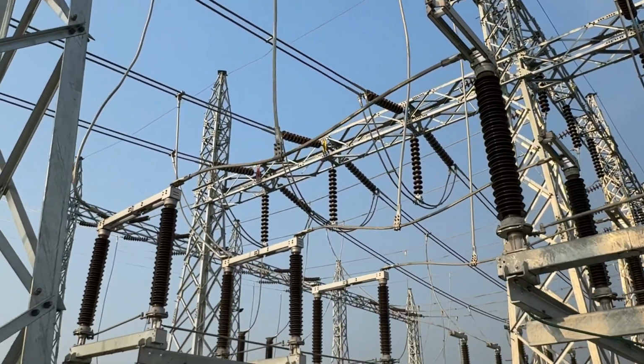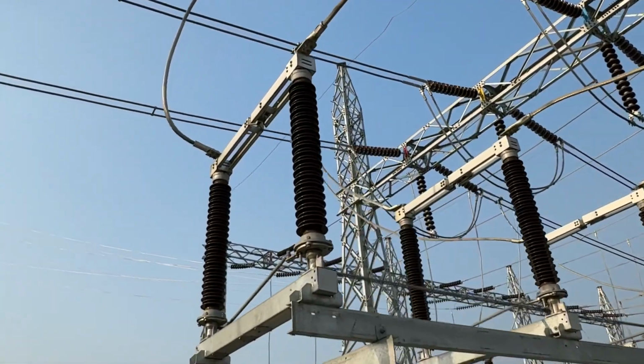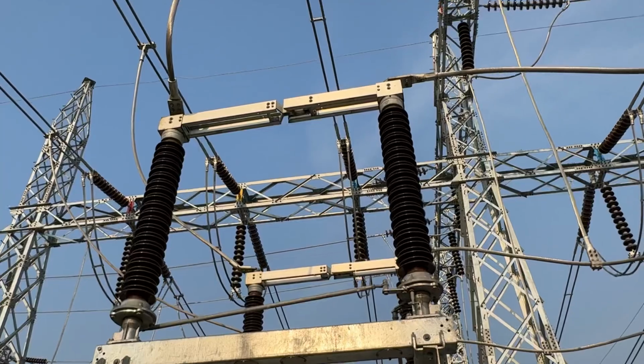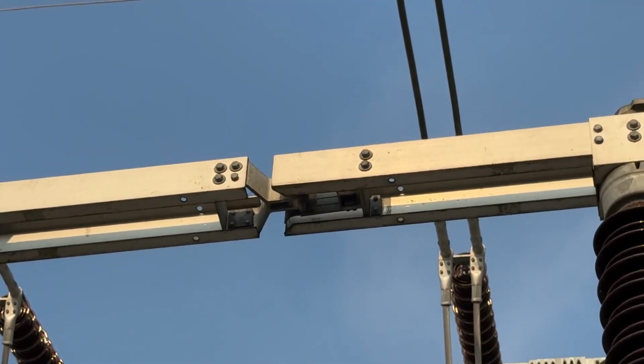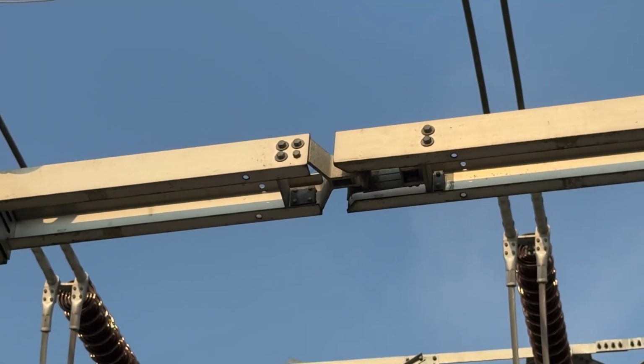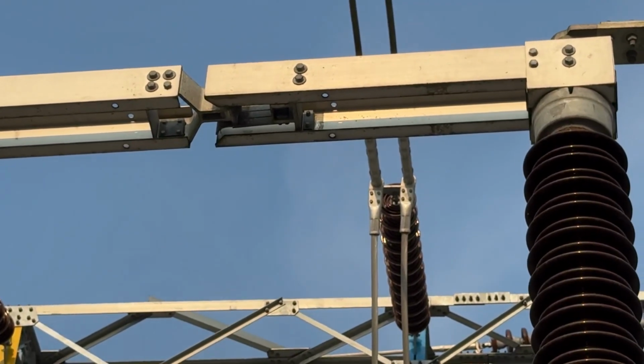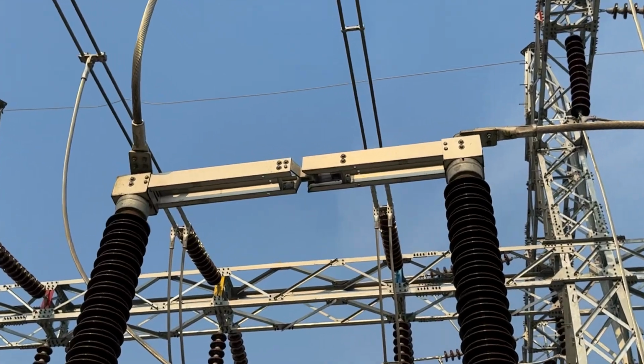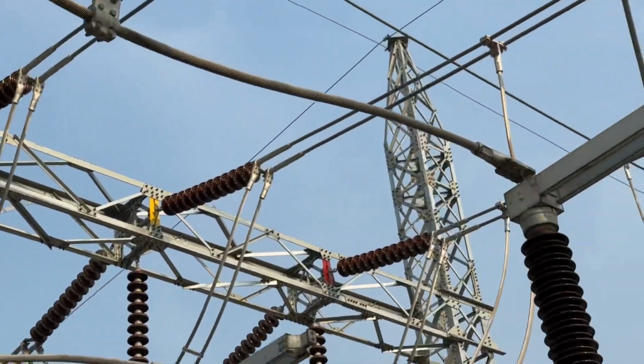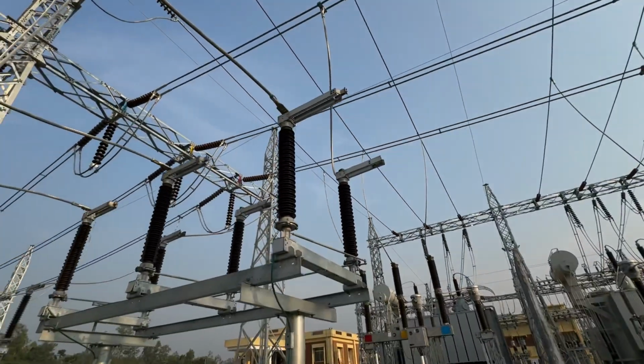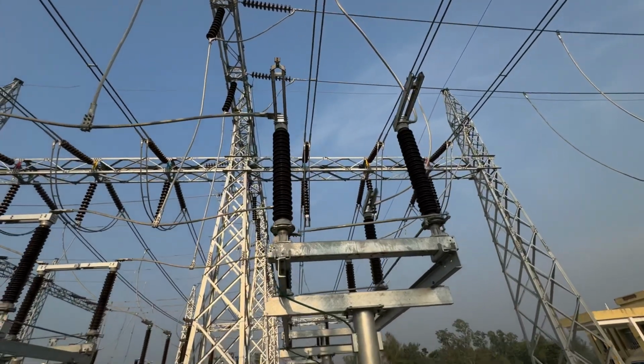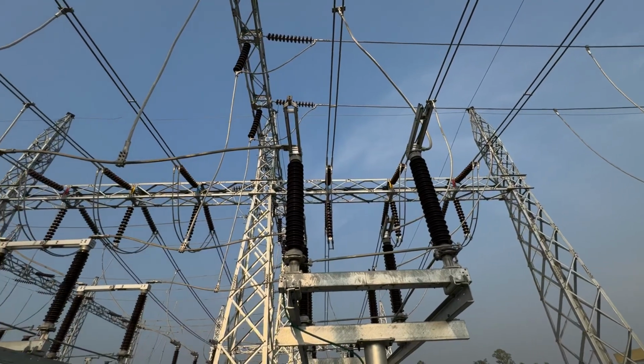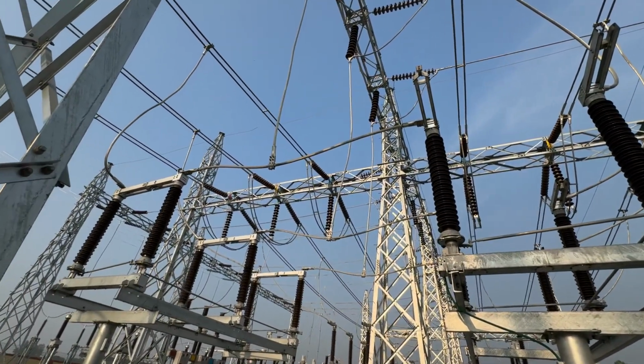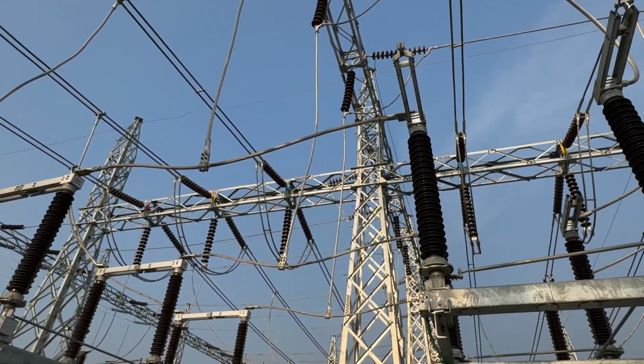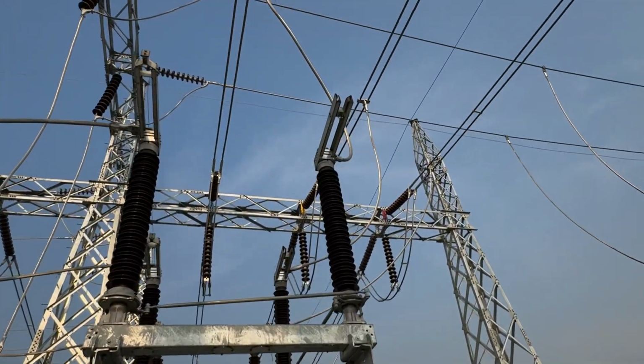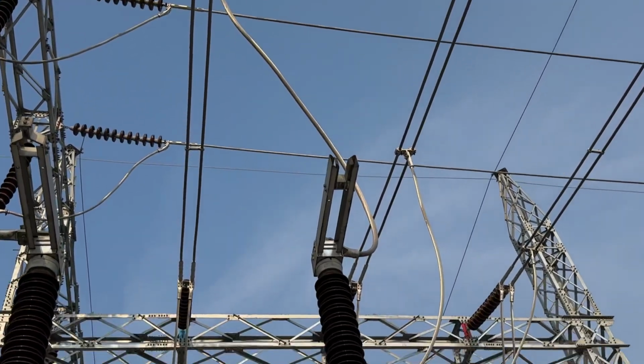Okay, now this isolator is in closed condition. Both male and female contacts are closed. Current flows from one contact to another. Voltage level at both contacts is the same, 132 kV. But what is the status of this open isolator? Here also there is voltage, because one side is connected with this another isolator, so voltage is here. The other end is connected with the bus. Bus is charged, so there is voltage also here.